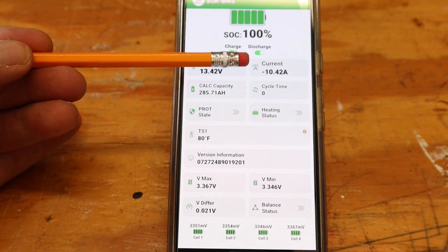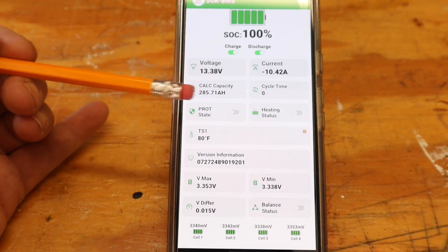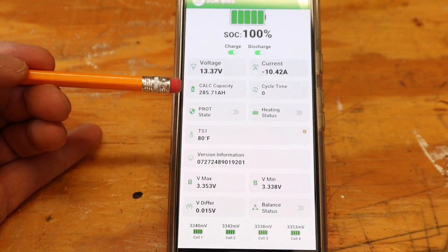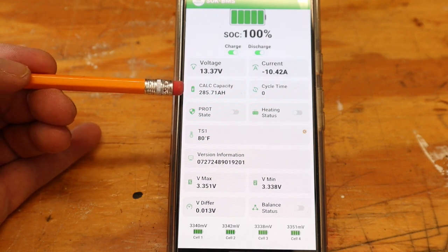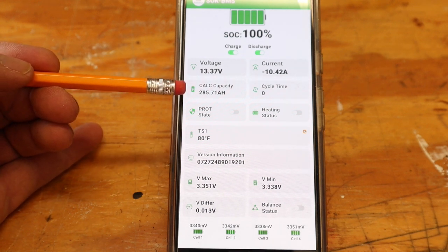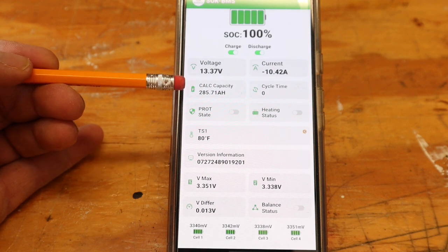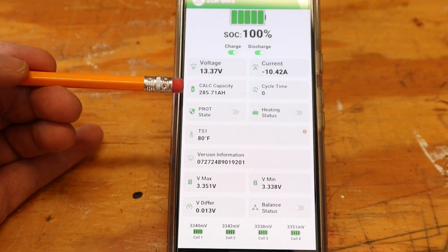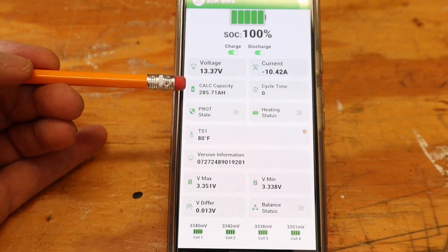It's discharging at 10.42 amps because I've got it on the load tester right now. The app has calculated the capacity at 285.71 amp hours. Even the manual says this may not be accurate until it cycles the battery a few times.